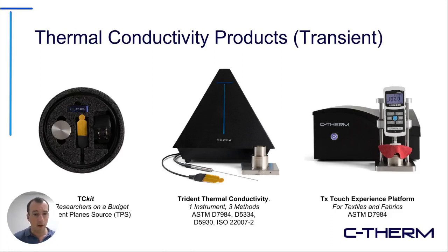It does offer a strong basic capability in measuring the conductivity of mostly solid materials, would work on most polymers certainly. Does not meet the ISO standard for TPS. For that, you need the bridge circuit technology that is built into Trident in the middle product picture. On the right of this, you have the TX Touch Experience platform.